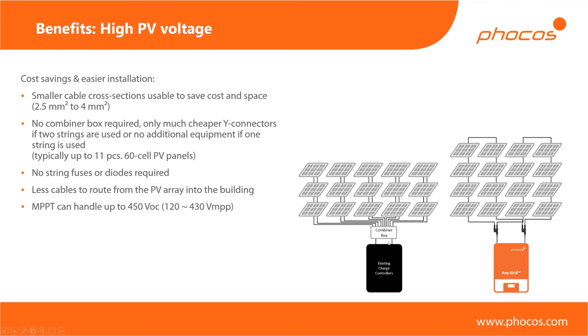So you can deal with very small cable cross sections, and pretty much the cables that come with your PV modules are all you need. You're not going to have to increase the wire cross section from that. So that already is a big cost saver there. You just save a lot of copper. Then, like I mentioned, you don't need a combiner box, which will add several $100s typically to your installation. No string fuses, no diodes.